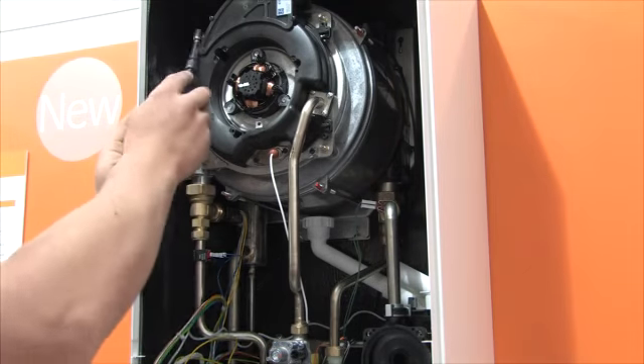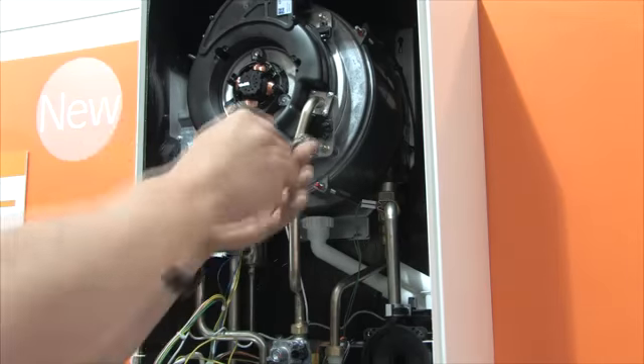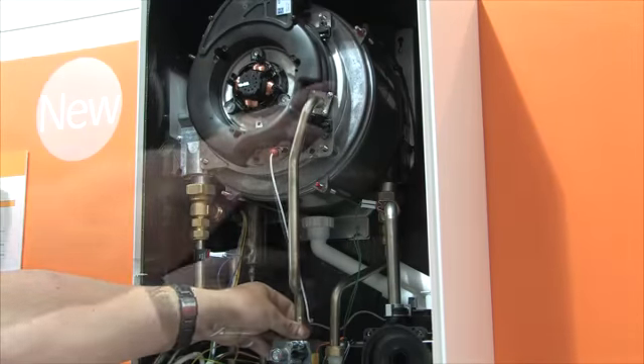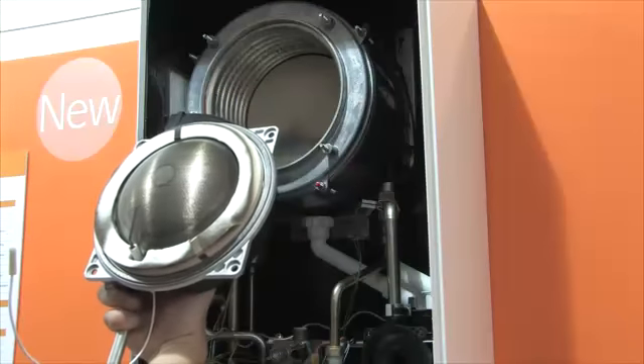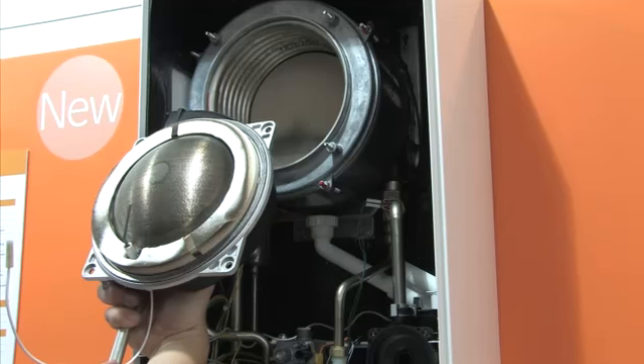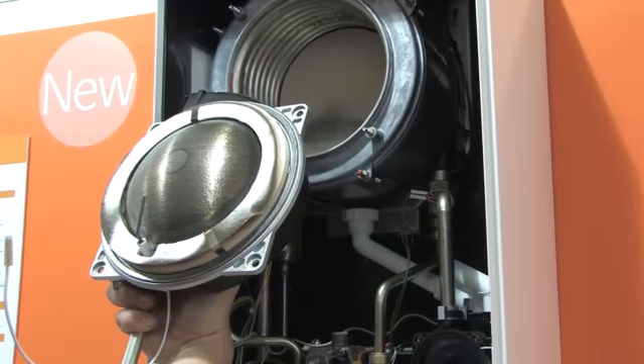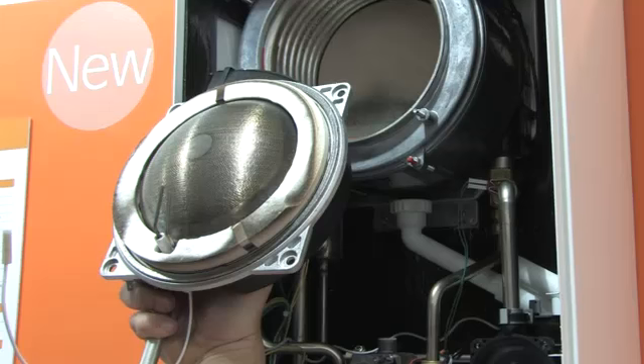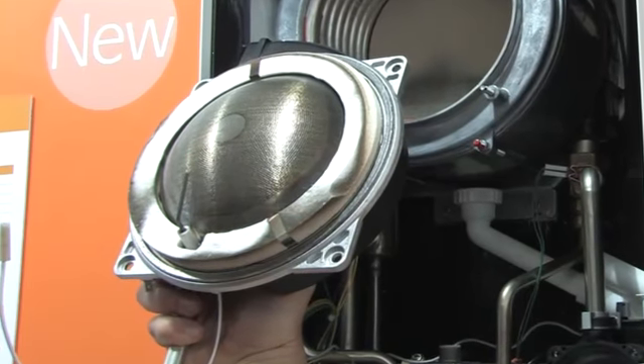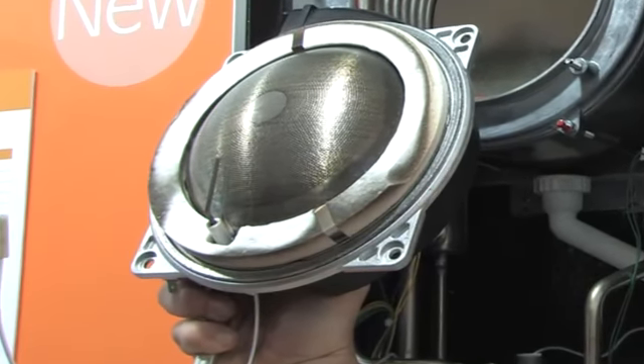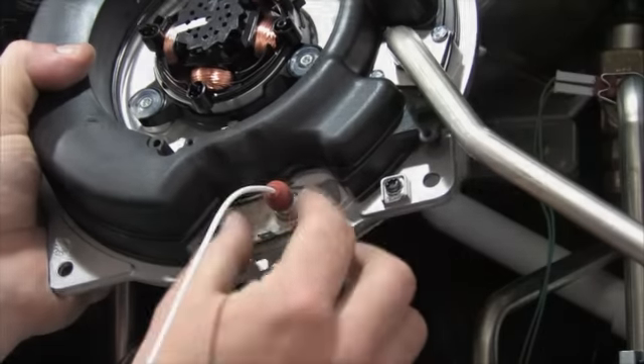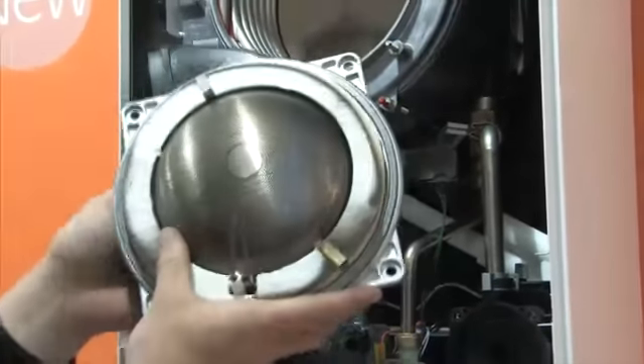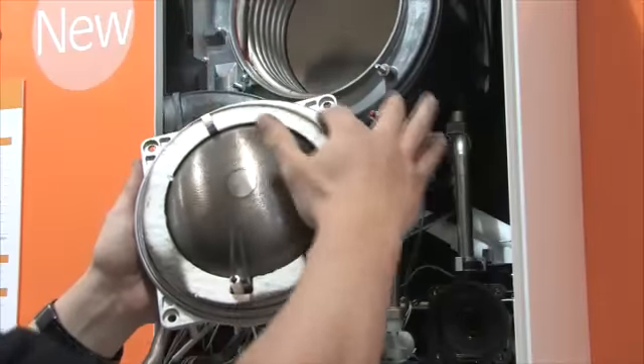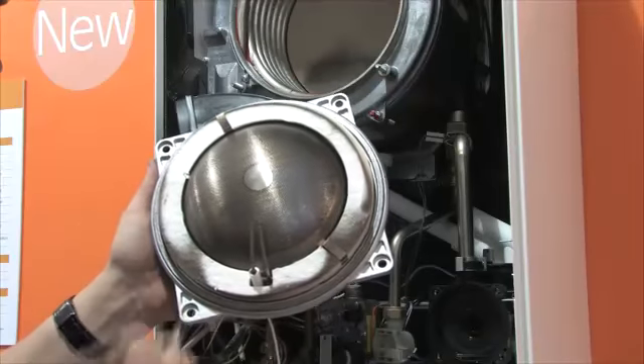Remove the burner via the 4 brass bolts located on the corners of the burner assembly. Slacken and remove the compression nut on top of the gas valve and pull the burner forward and out. A unique feature of the Modena is the stainless steel dome burner, which allows debris and residue to simply fall off rather than build up and cause blockages of the burner ports. The ignition electrodes can be removed without removing the burner, and because it is so resilient, the graphite seal only requires regular inspection, so it should never wear out during the lifetime of the boiler.